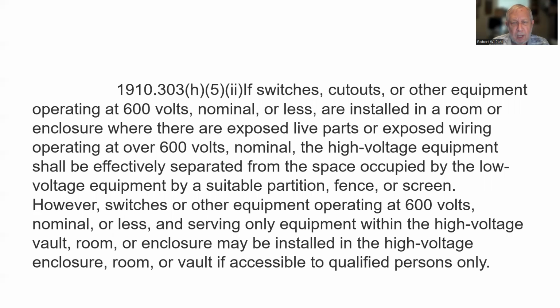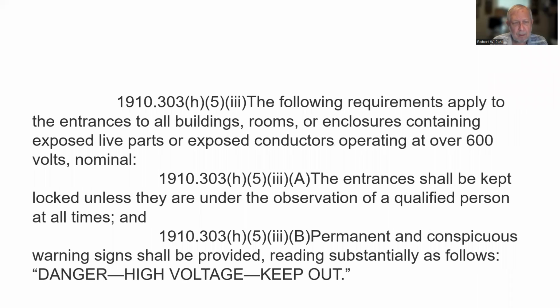Here's H5. If switches, cutouts, or other equipment operating at 600 volts nominal or less are installed in a room or enclosure where there are exposed live parts or exposed wiring operating at over 600 volts nominal, the high voltage equipment shall be effectively separated from the space occupied by the low voltage equipment by a suitable partition, fence, or screen. However, switches or other equipment operating at 600 volts nominal or less and serving only equipment within the high voltage vault room or enclosure may be installed in the high voltage enclosure room or vault if accessible to qualified persons only. Now they get pretty technical.